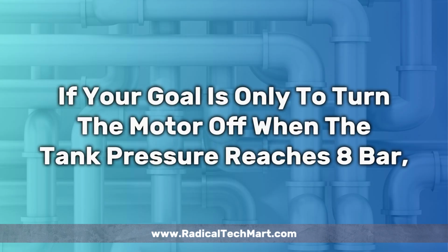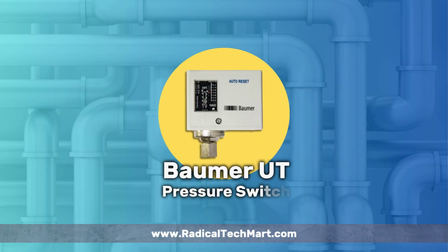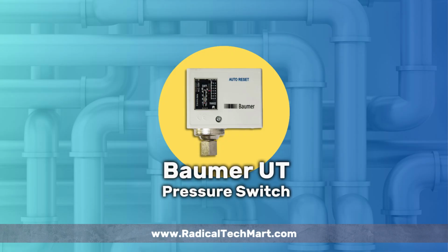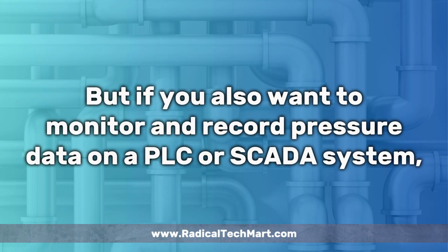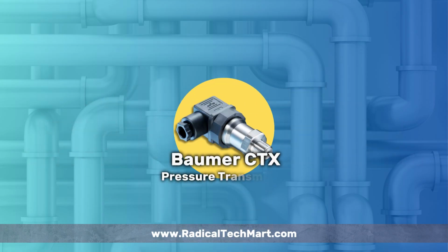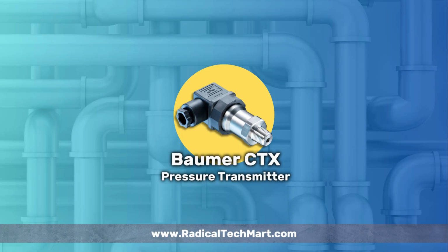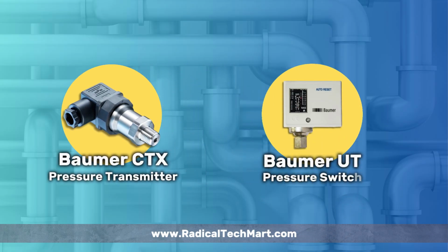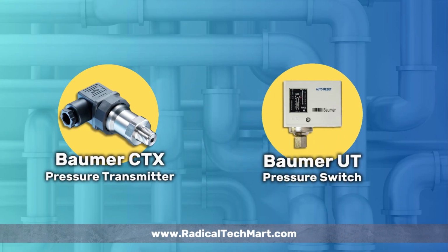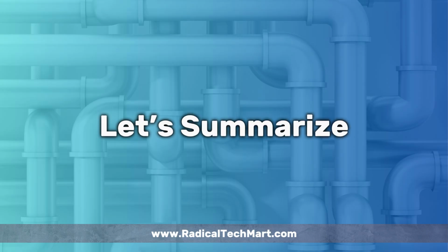If your goal is only to turn the motor off when the tank pressure reaches 8 bar, a Baumer UT pressure switch is the perfect solution, simple and reliable. But if you also want to monitor and record pressure data on a PLC or SCADA system, you'll need a Baumer CTX pressure transmitter. In many plants, both are used together, the switch for control and the transmitter for monitoring and data logging.